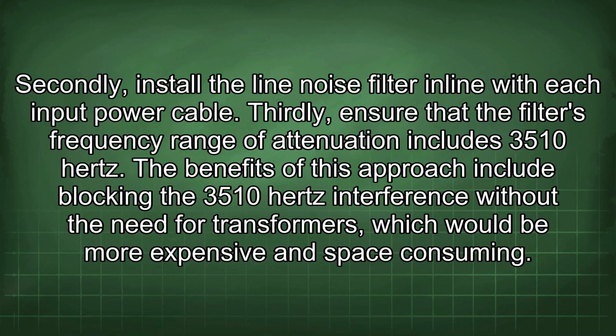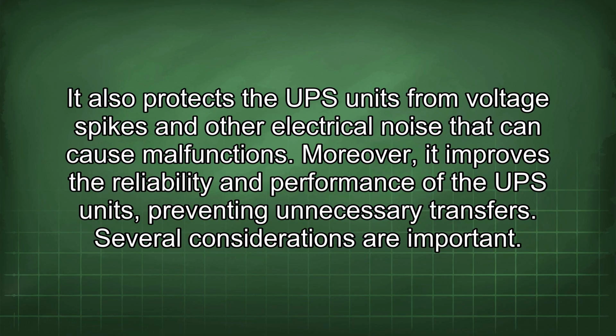The benefits of this approach include blocking the 3,510 Hz interference without the need for transformers, which would be more expensive and space-consuming. It also protects the UPS units from voltage spikes and other electrical noise that can cause malfunctions. Moreover, it improves the reliability and performance of the UPS units, preventing unnecessary transfers.